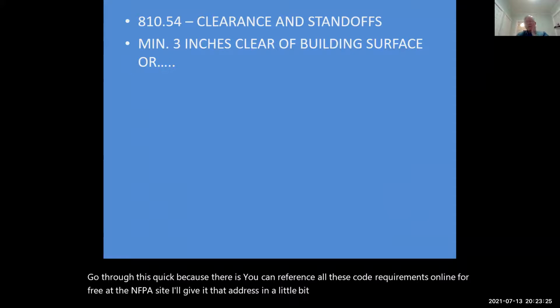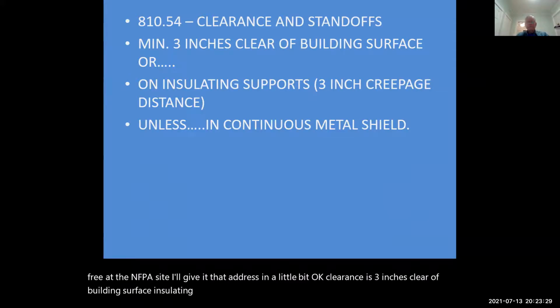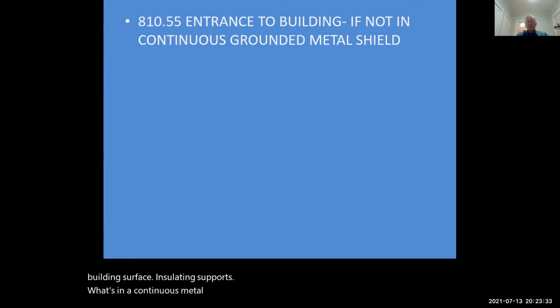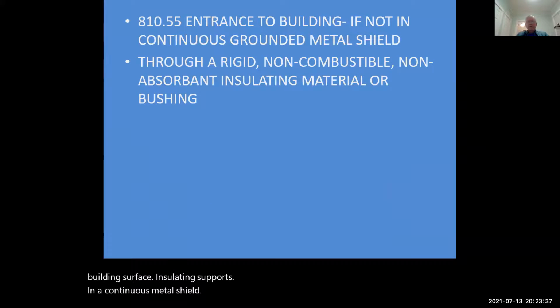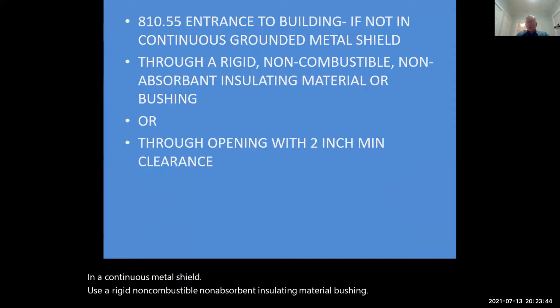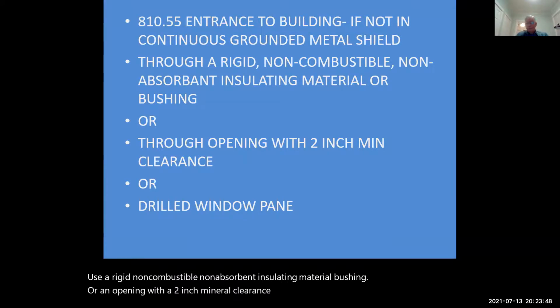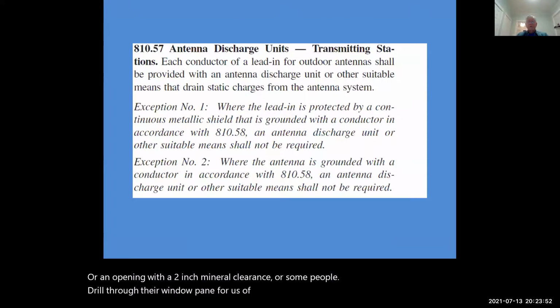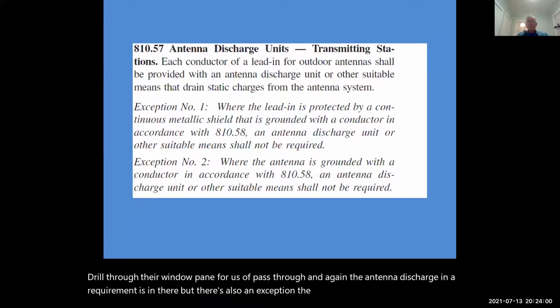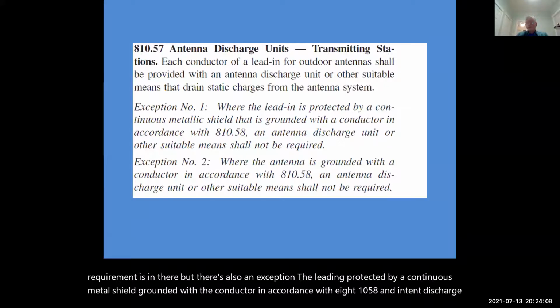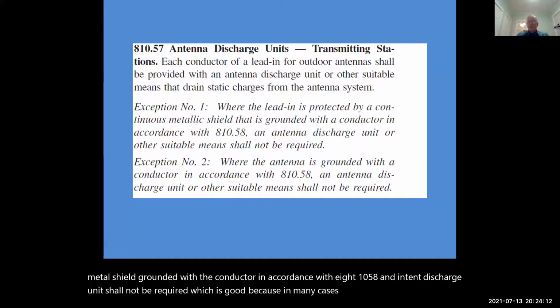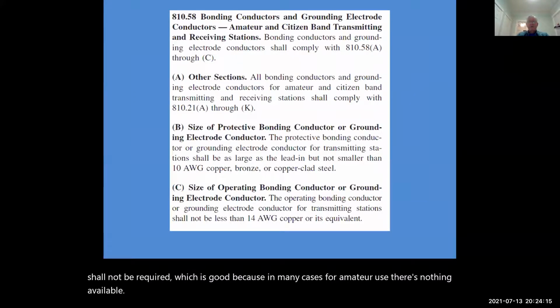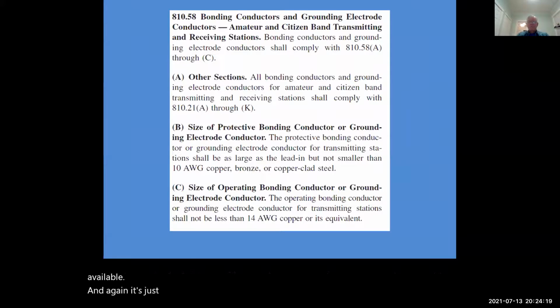Okay, clearances: 3 inches clear of building surface, insulating supports, unless it's in a continuous metal shield. Use a rigid, non-combustible, non-absorbent insulating material or bushing, or an opening with a 2-inch minimum clearance, or some people drill through their window pane for a pass-through. And again, the antenna discharge unit requirement is in there, but there's also an exception: the lead-in protected by a continuous metal shield, grounded with a conductor in accordance with 810.58. An antenna discharge unit shall not be required, which is good because in many cases for amateur use, there's nothing available. Again, just the sizes are in there.